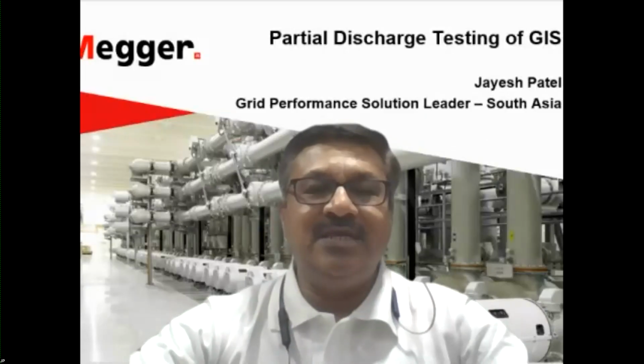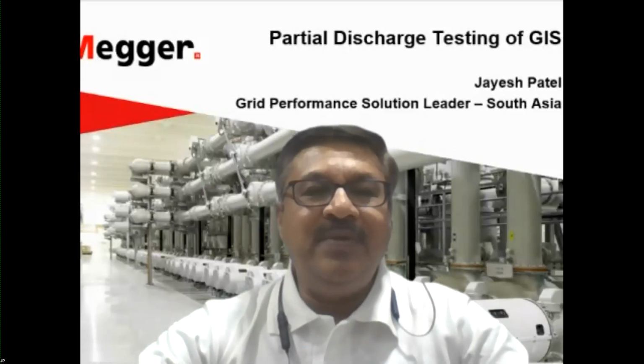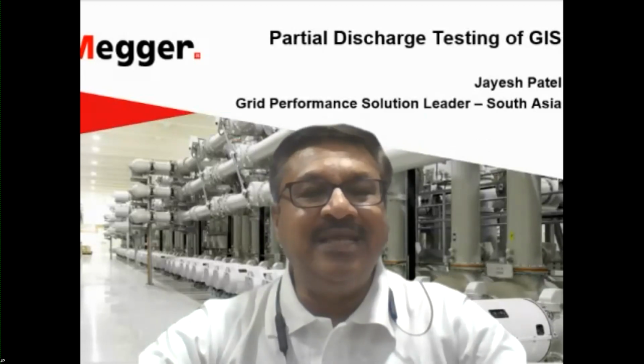Sir, synchronization is very simple. Every PD instrument has a synchronization input. This synchronization input is basically connected with the VT signal, which you can receive from anywhere inside your substation. Basically, you have to provide the same voltage signal which is being fed to your GIS to this synchronization input, so that the phase information is obtained.